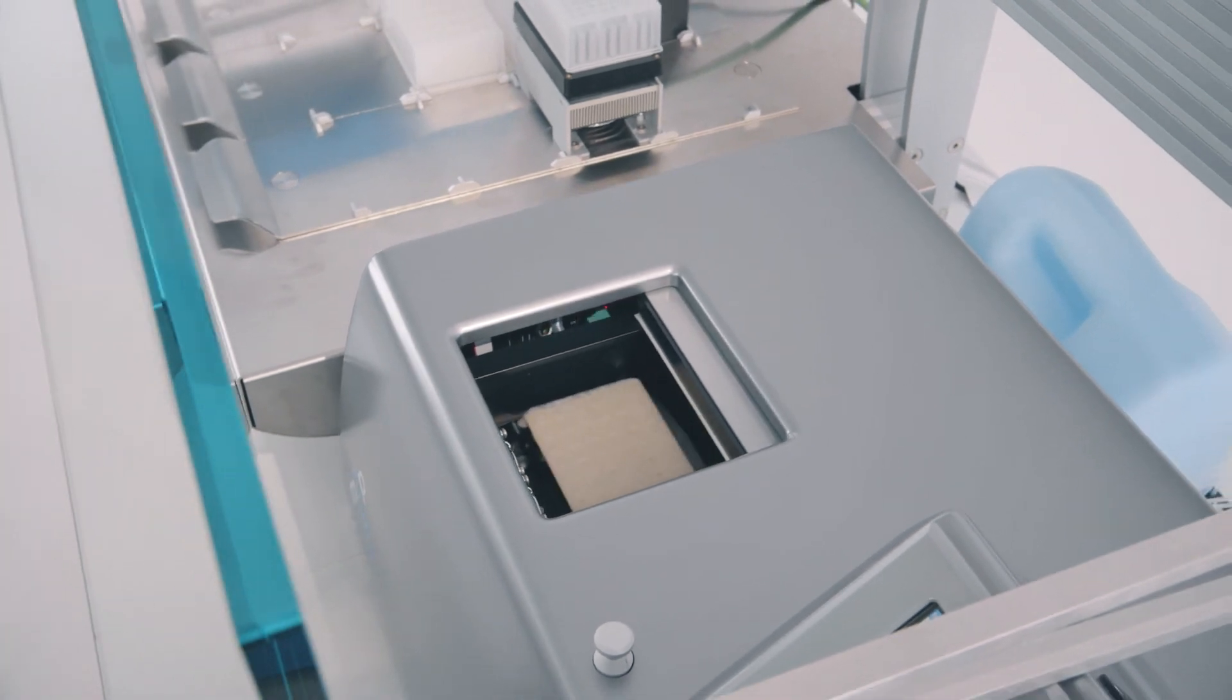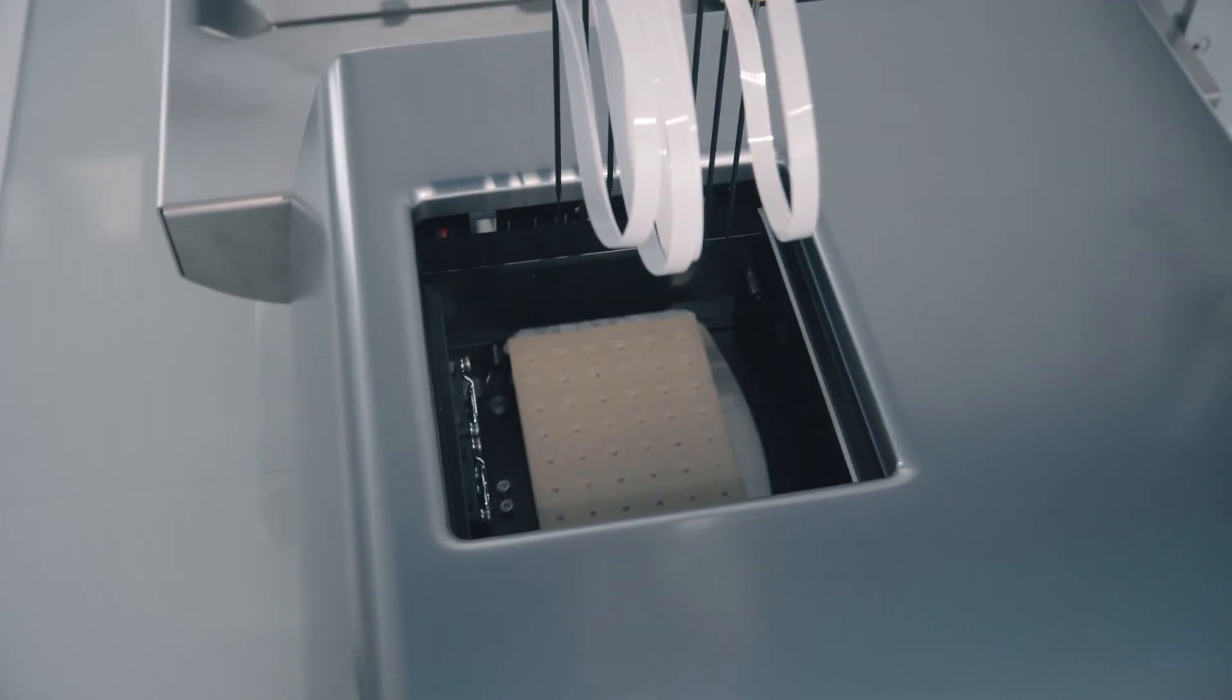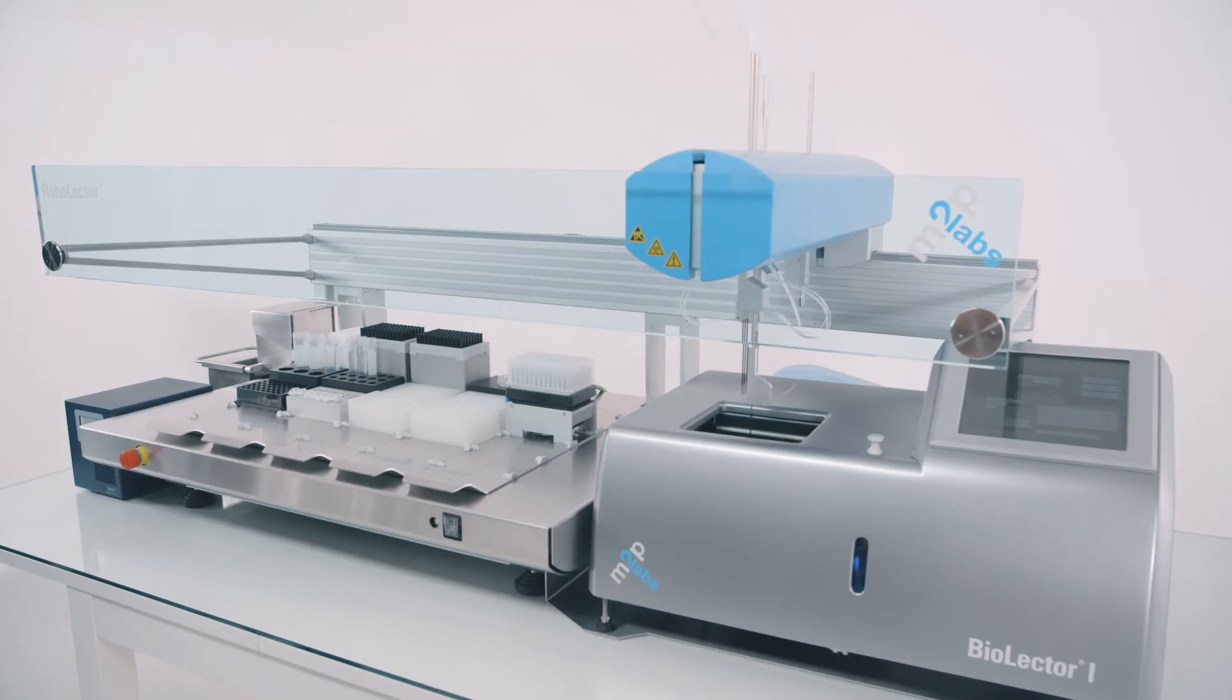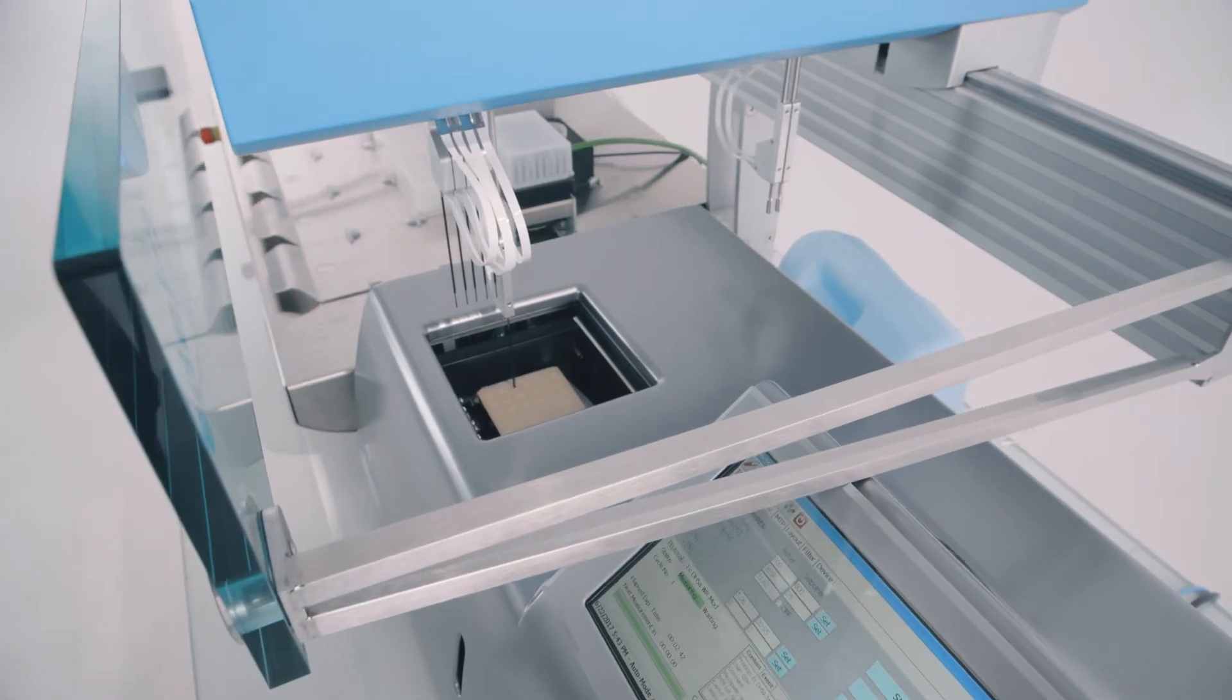The Robolector takes samples from selected or all wells of the shaking MTP while the Biolector is still operating. The preset Robolector agent is triggered by either process time or Biolector signal.